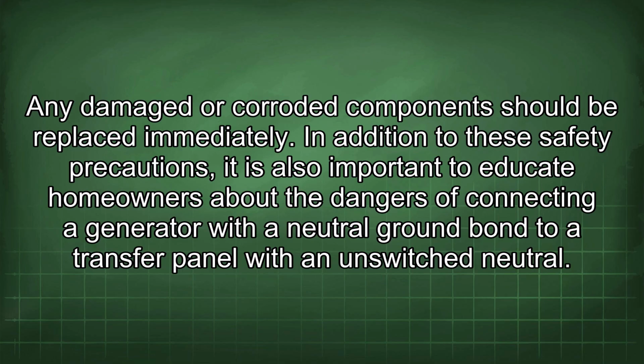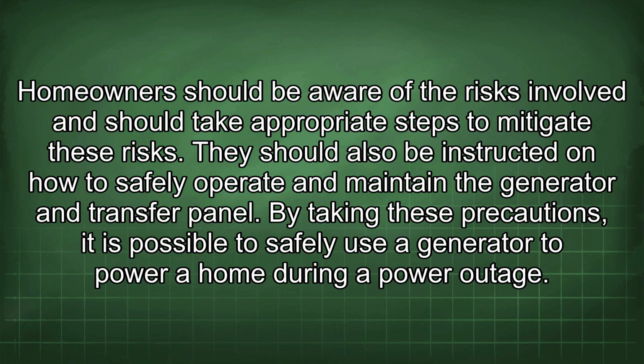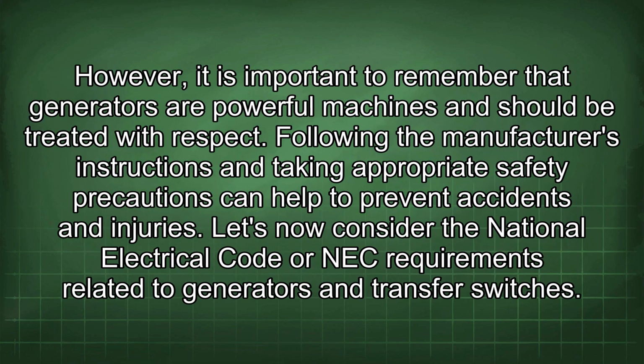In addition to these safety precautions, it is also important to educate homeowners about the dangers of connecting a generator with a neutral ground bond to a transfer panel with an unswitched neutral. Homeowners should be aware of the risks involved and should take appropriate steps to mitigate these risks. They should also be instructed on how to safely operate and maintain the generator and transfer panel. By taking these precautions, it is possible to safely use the generator to power a home during a power outage. However, it is important to remember that generators are powerful machines and should be treated with respect. Following the manufacturer's instructions and taking appropriate safety precautions can help to prevent accidents and injuries.